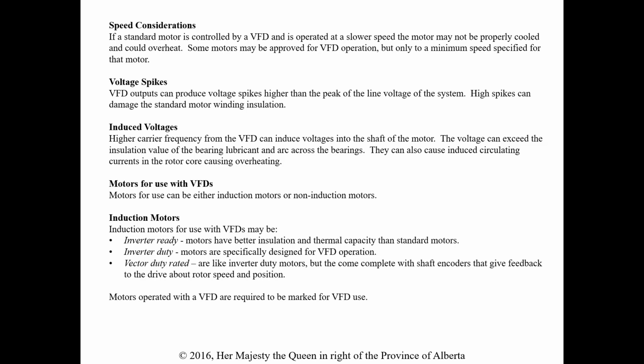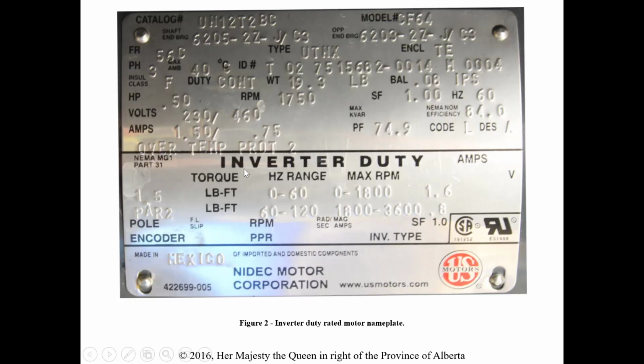So they need to be marked for VFD use. So here's an example of an inverter duty rated motor nameplate right out of your module. You can see your frequency ranges based on your foot-pounds torque, and then also your maximum RPM based on those frequencies. So we can see we have a range here, so that tells us that we can vary the speed to this motor.